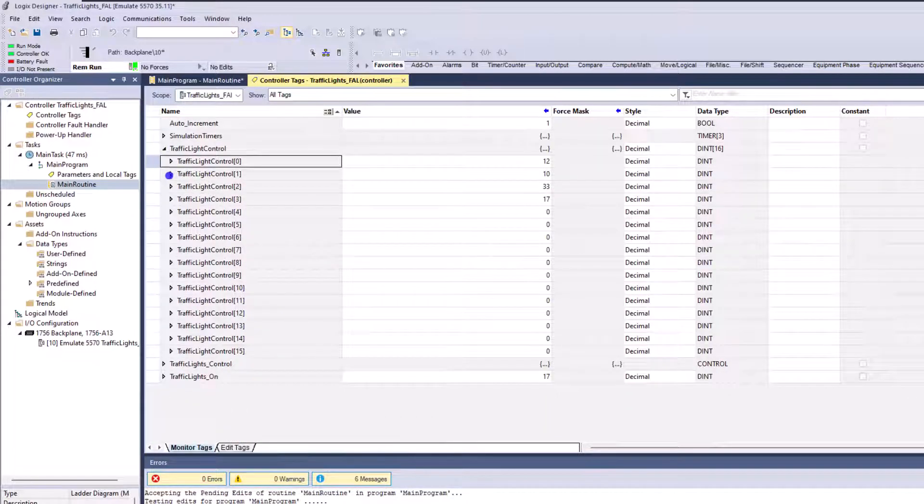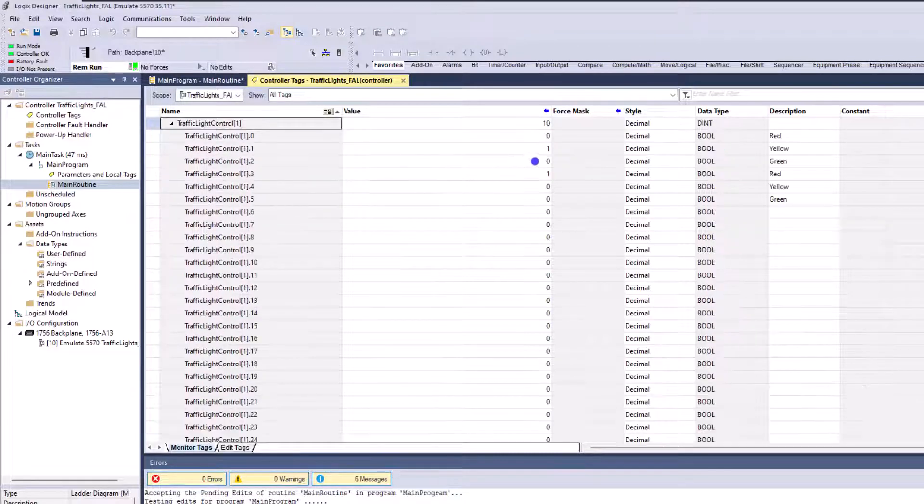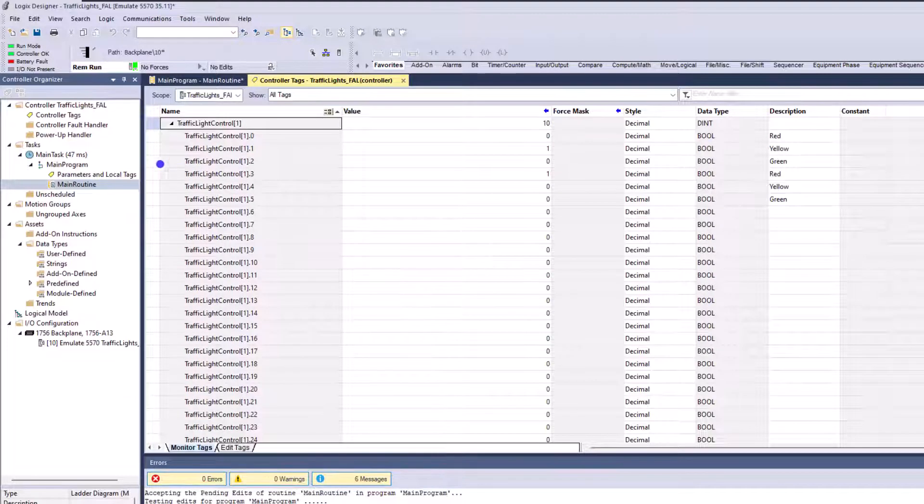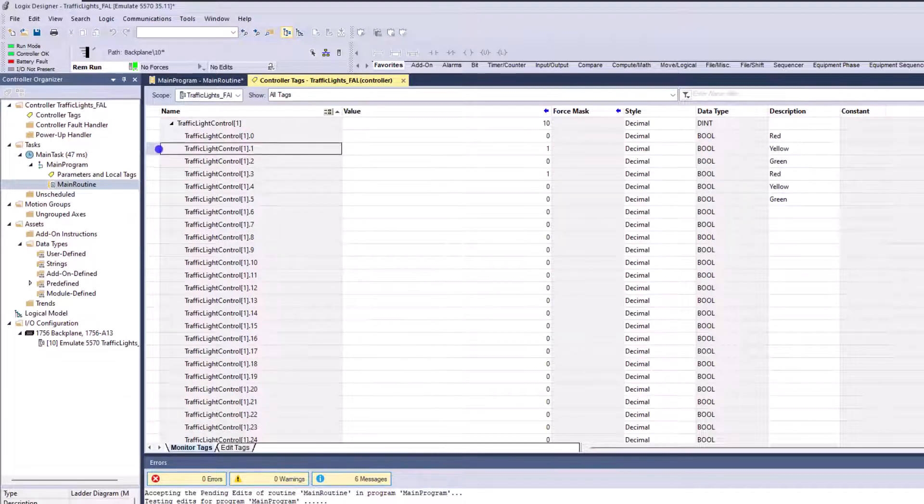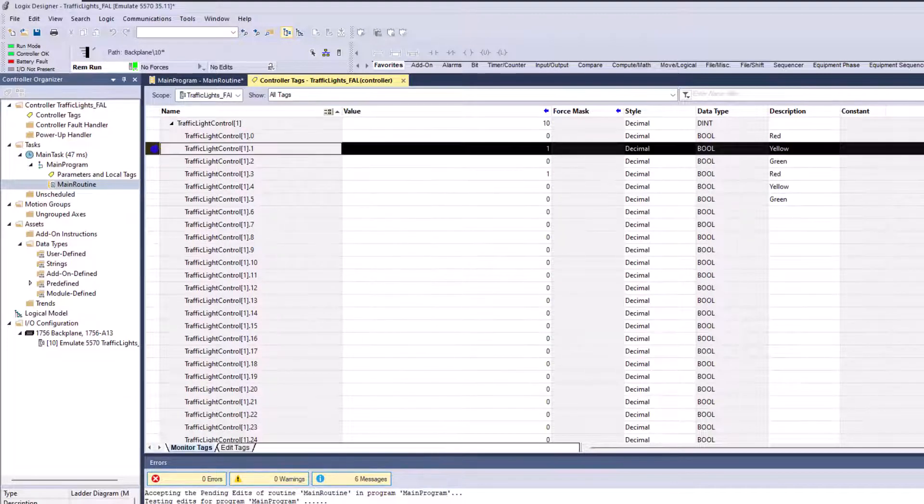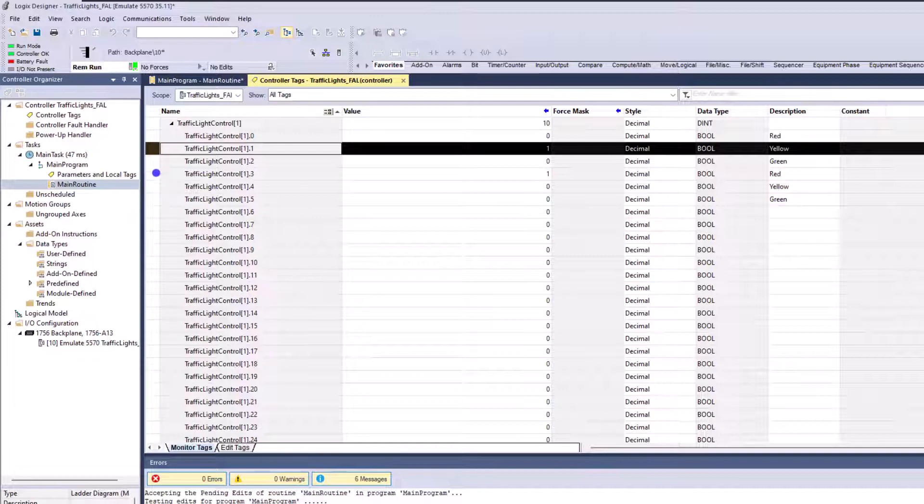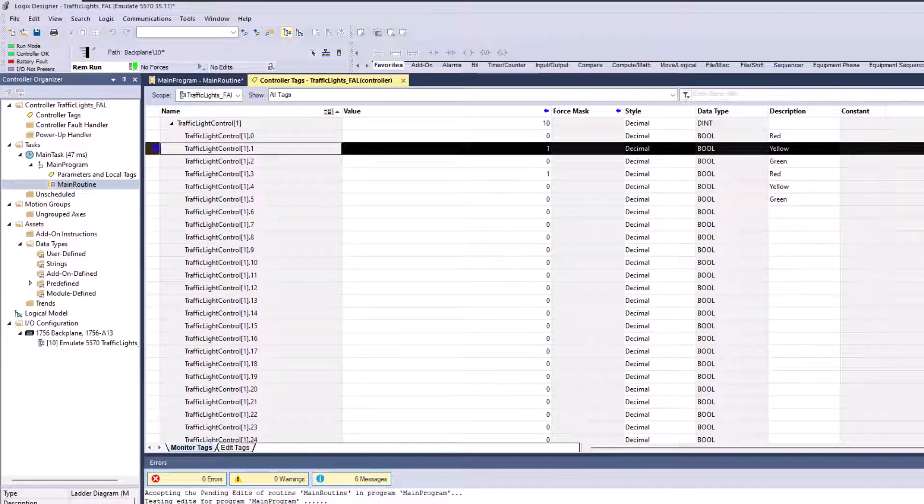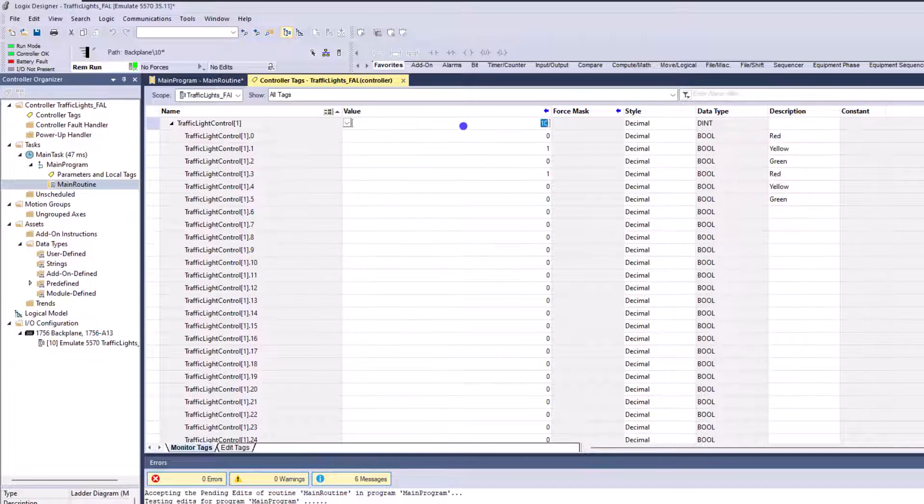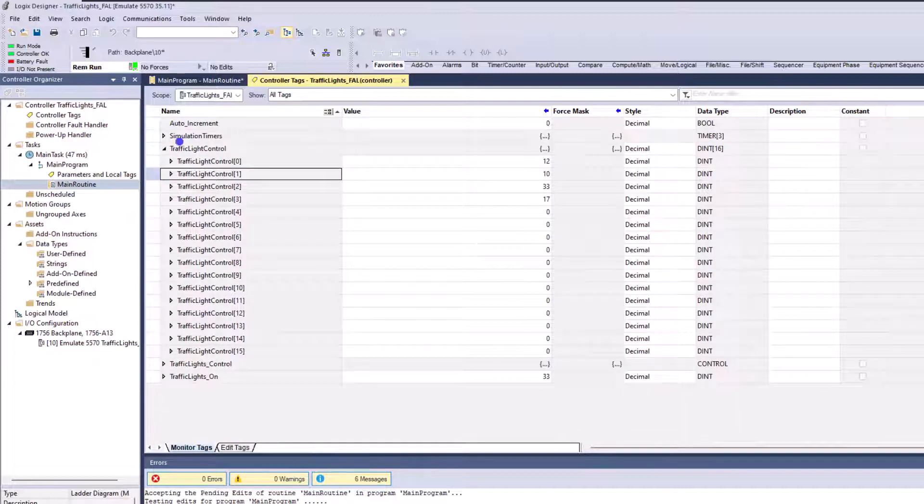Second thing is, if the FAL instruction position is pointing to one, then I want to come in here and turn on this bit right here and this bit right here. So I'm keeping the red on, and then I'm going to turn on the yellow. Now that is a decimal value of 10. So I'm breaking that down in binary coded decimal.